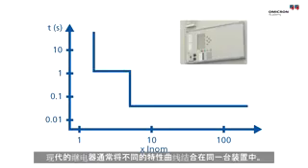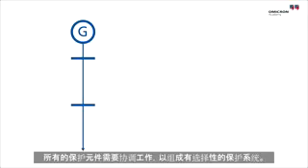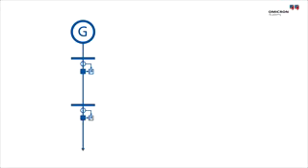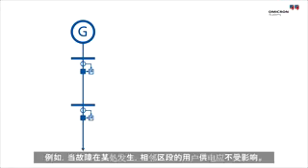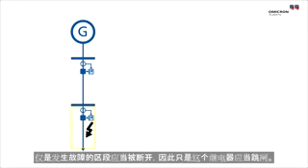Modern relays usually combine different curves within one housing. The complete protection system also includes elements residing in a number of other relays. All protective elements need to work together in order to form a selective system. For instance, when a fault occurs here, it should not affect the electrical supply of customers in the neighboring segment. Only the affected segment should be switched off. Thus, only this relay should trip.